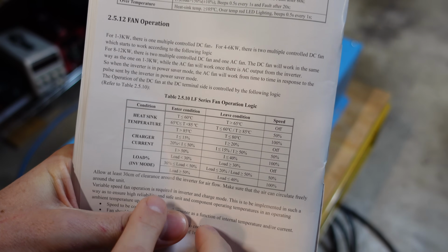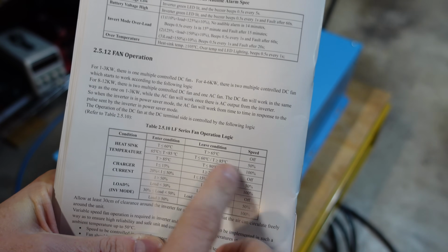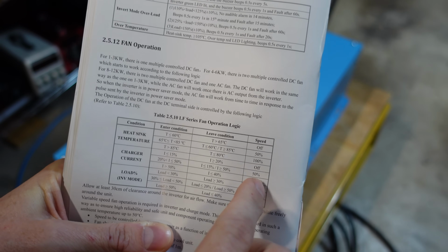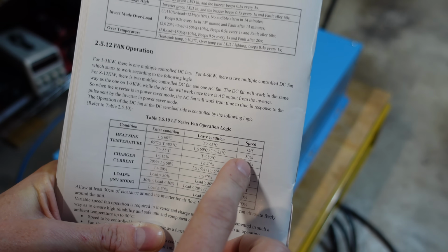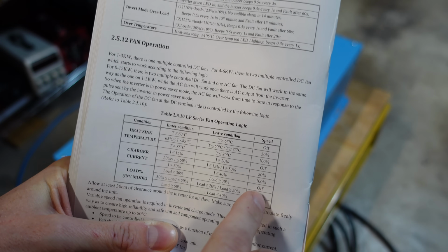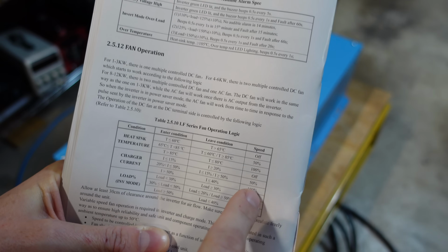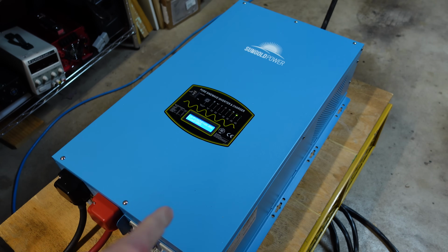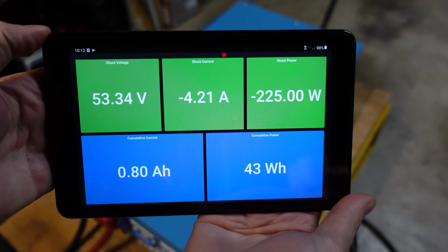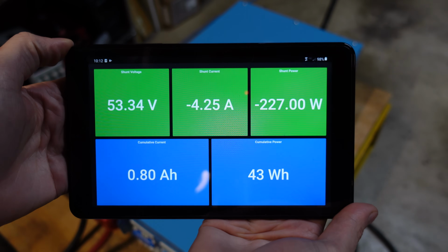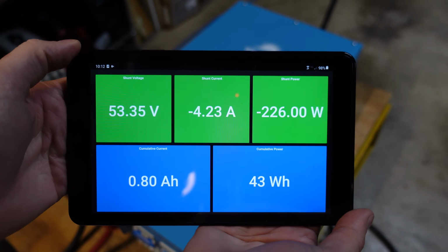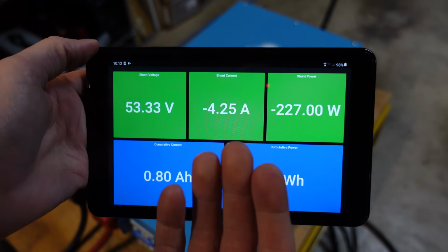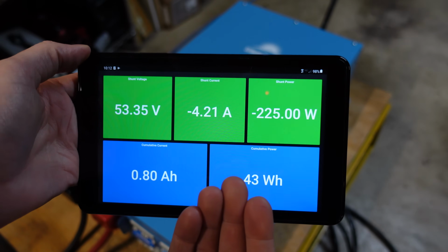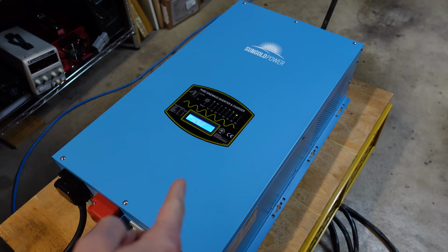So I'm kind of surprised to hear that fan running because there is no load on it. The charger is not connected, and the heatsink, it's very cold in here, so this fan should be off with all of these conditions met. I'm not sure why that fan is running on this unit with it idling like that. It is pulling 227 watts idle, mostly because of that fan, I'm guessing, because according to the manual this should be around 180 watts of idle. So I don't know what's up with that.